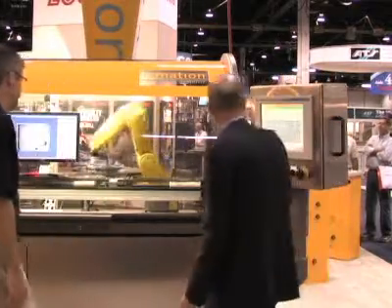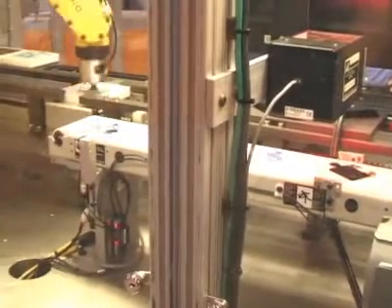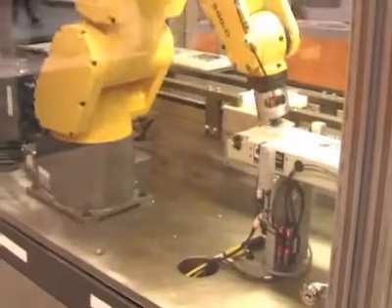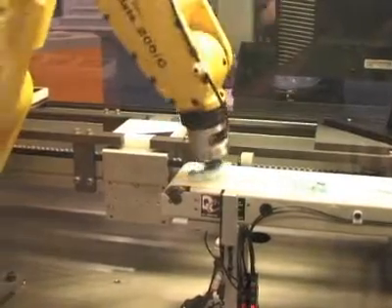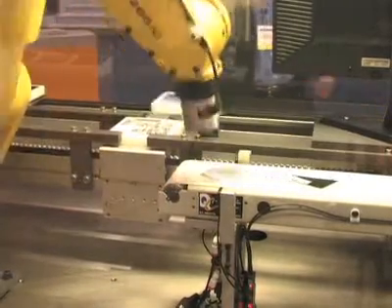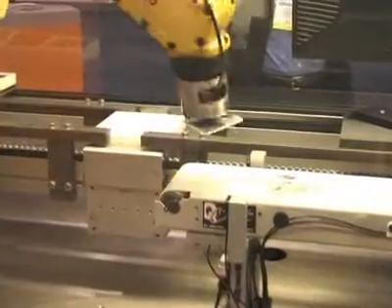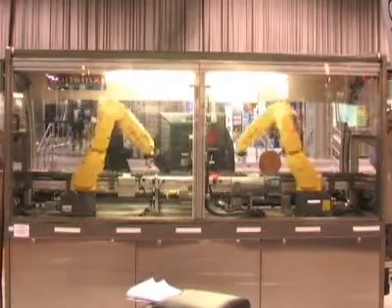This is a show machine, so it won't have nearly as much automation as a typical build. For safety requirements, we always do a risk assessment before we design the control circuit. As a general practice, we always start with a Category 3 circuit — a fully redundant e-stop and guard circuit. One of the big game-changers we see in the industry right now is the ease of implementing a Category 3 safety circuit.